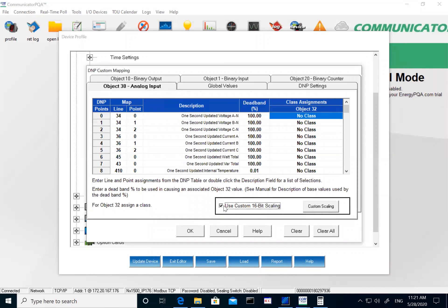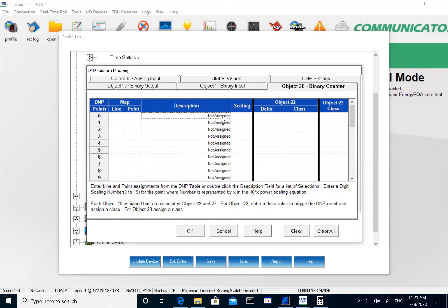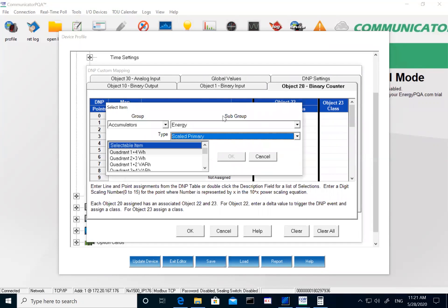For this example I'll use 32-bit since I want to have full resolution on my DNP values, so I'll leave it at 32-bit and uncheck 16-bit. There are also other tabs — for example, object 20 is binary counters. Counters in DNP are basically all your accumulators, so energy is an accumulator. Also, if you are reading pulses from different meters — like water or gas meters — you can tie those pulses into a Nexus meter and read them from the DNP side. Those all get configured on object 20.